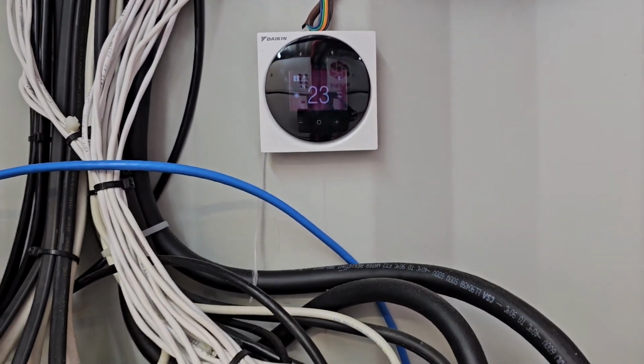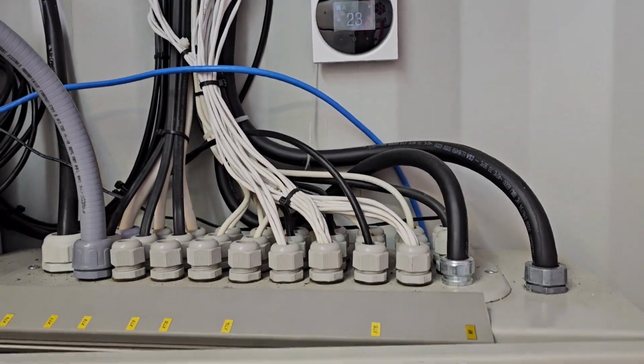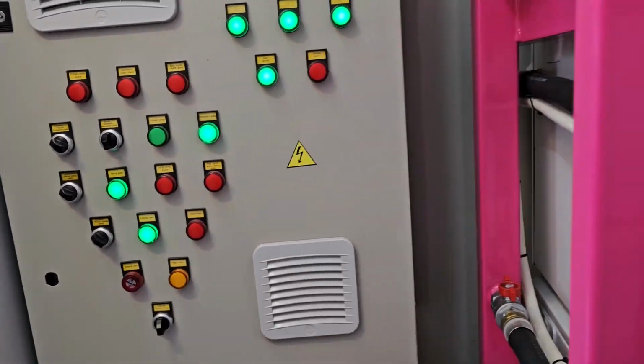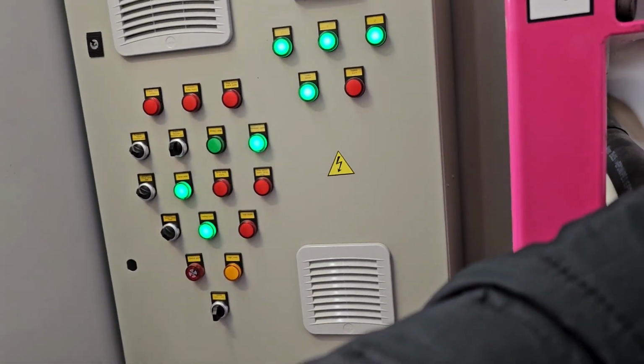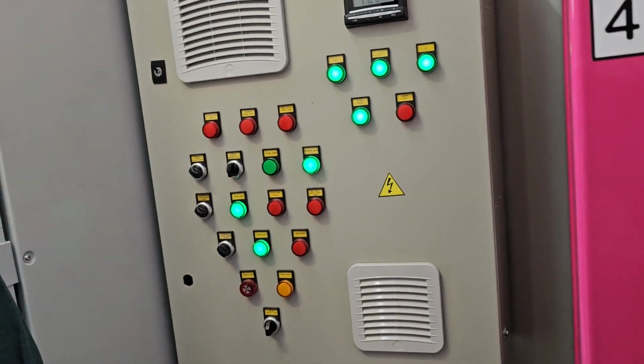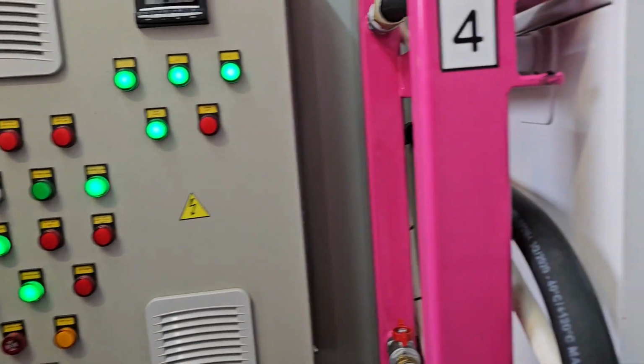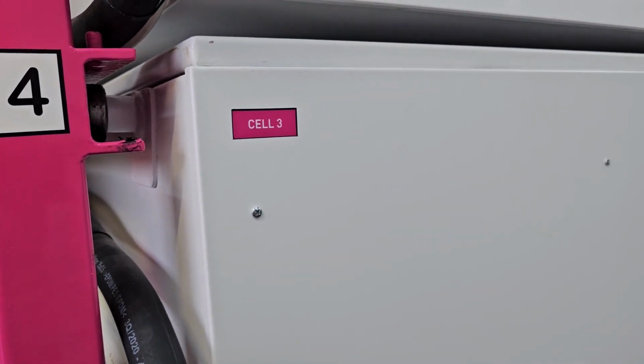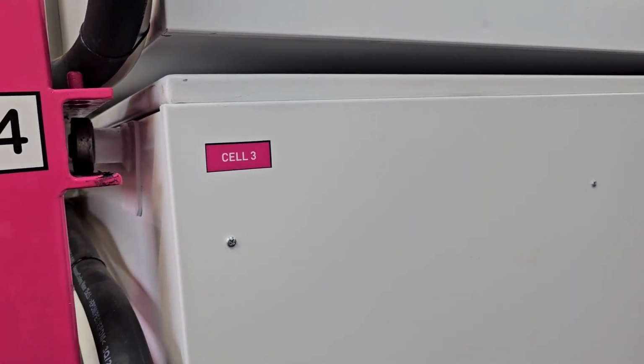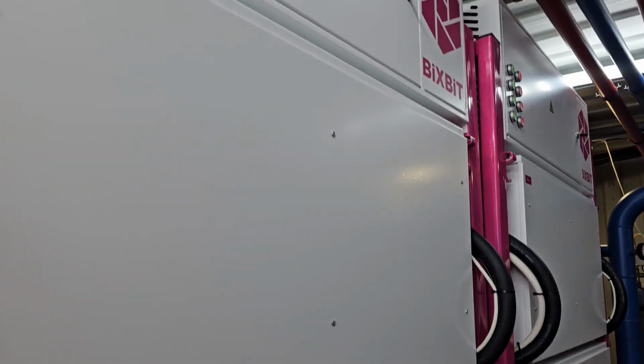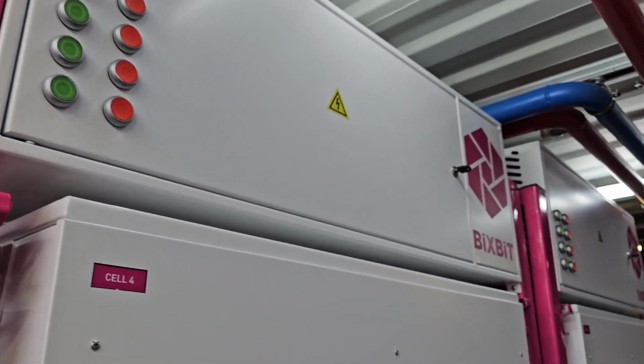Is this the thermostat for inside the container currently? Yes sir. Do we know temperatures of each container right now, or do you have to be in the firmware for that? I know the chip temperatures never get above 62 or 63. That's really good, even in 108 degree weather. With our system, our cooling tower just ramps up and down, normally it's not running full bore. We'll show you the cooling tower in one second, guys.